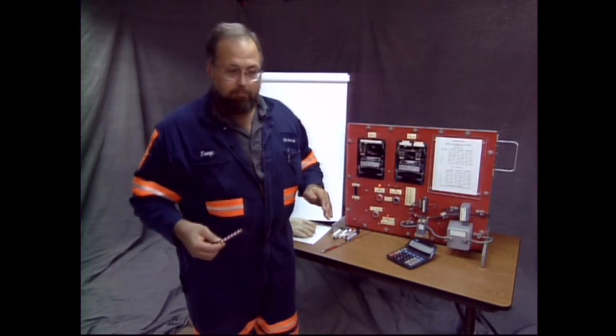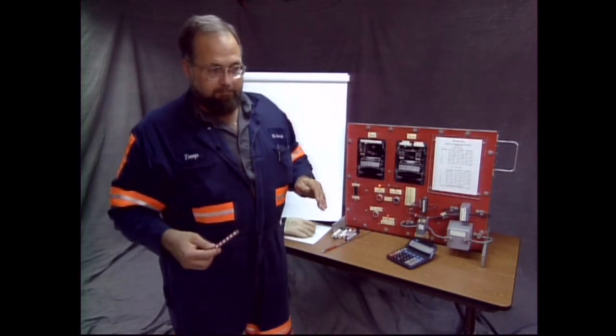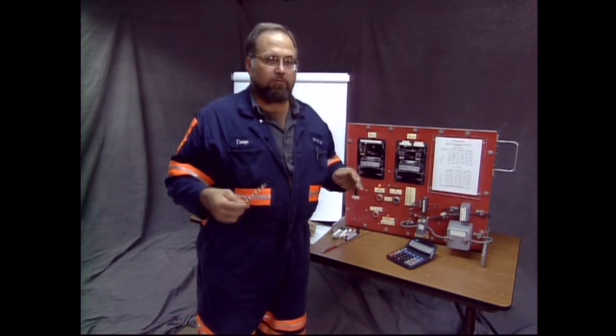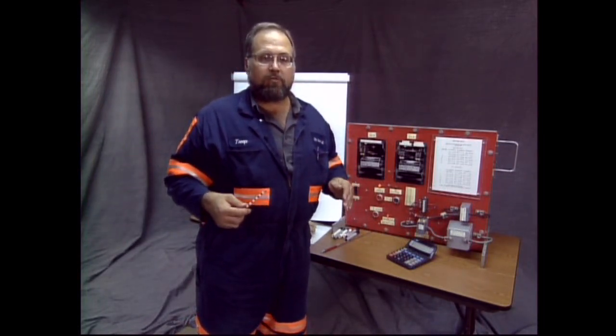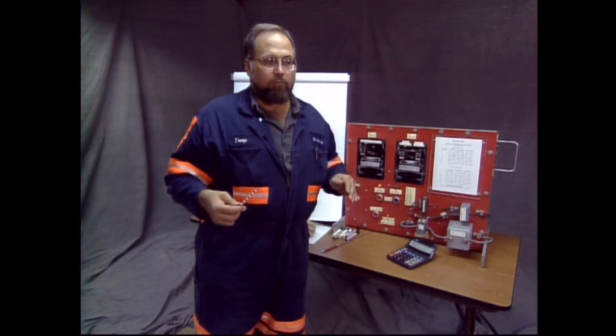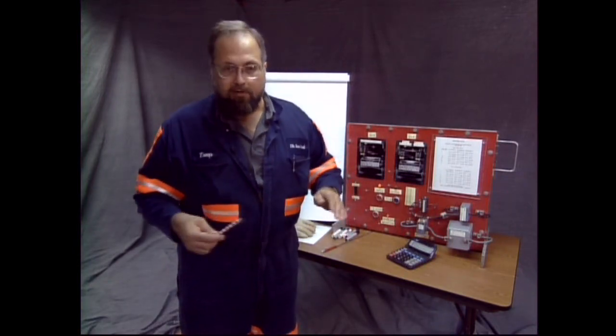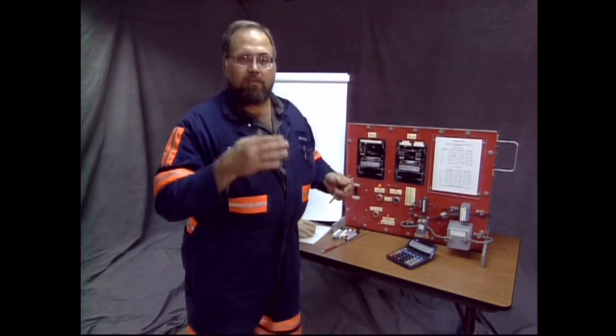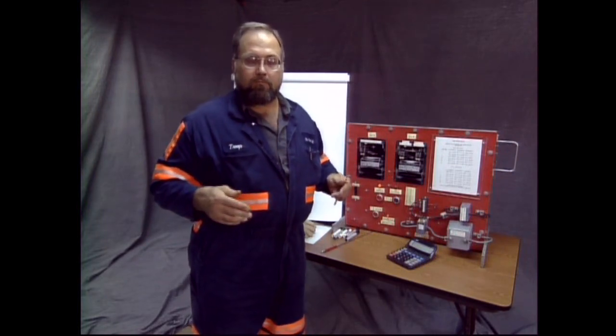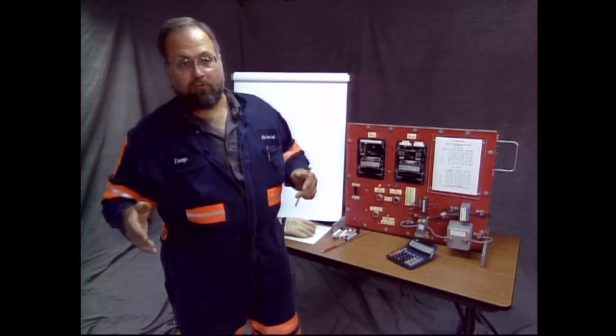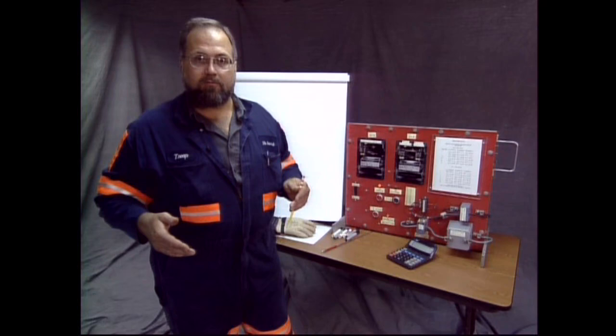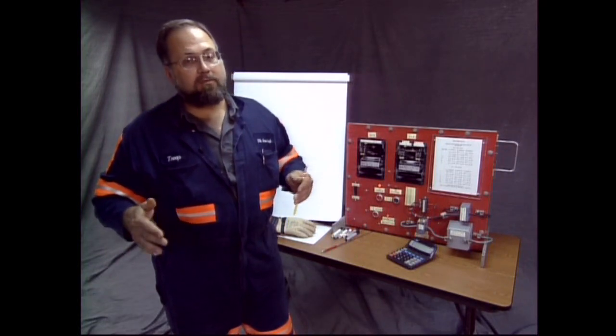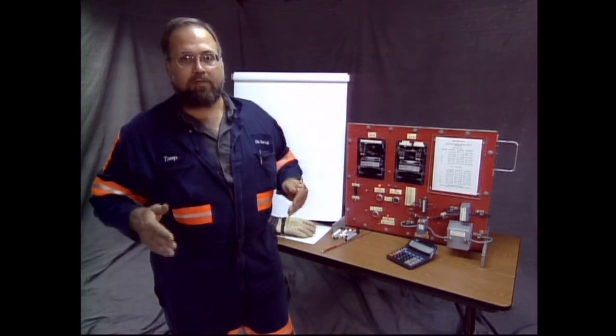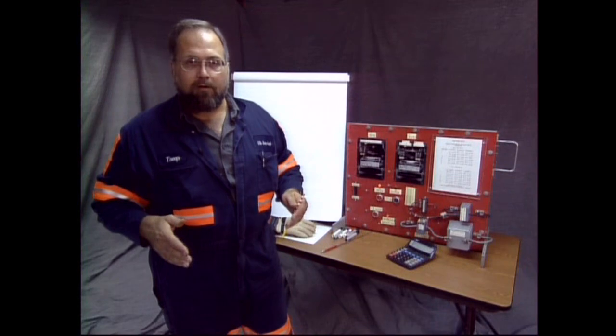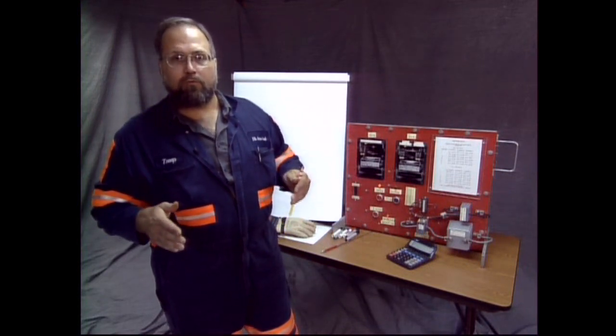And then most of our breakers and boxes here, our switch houses are equipped with a grounding bus that when you operate the visibles, the phases come against a ground bus. But if you don't have that, then you're going to have to manually attach grounds. But either way, easy or not so easy, it has to be done. You have to ground this high voltage circuit before you work on it.